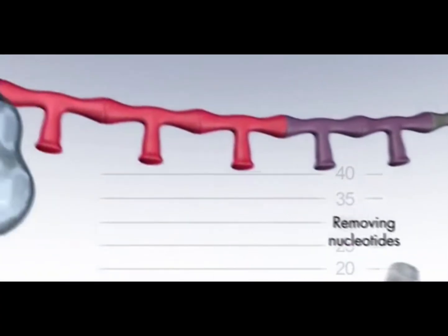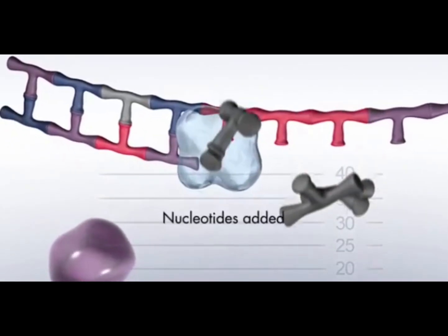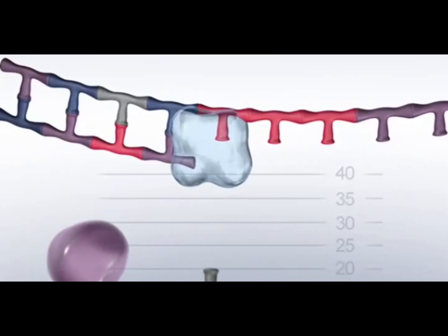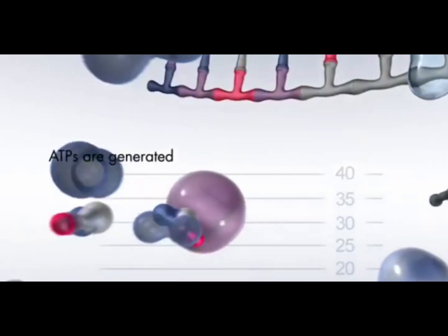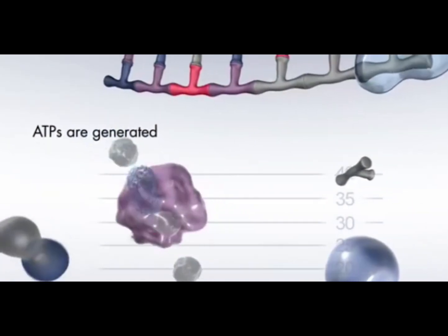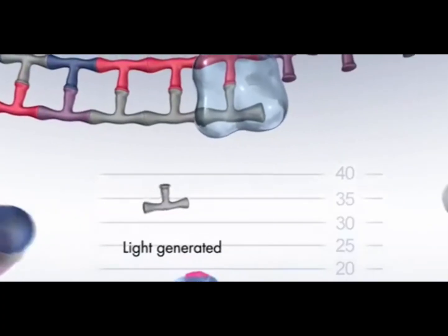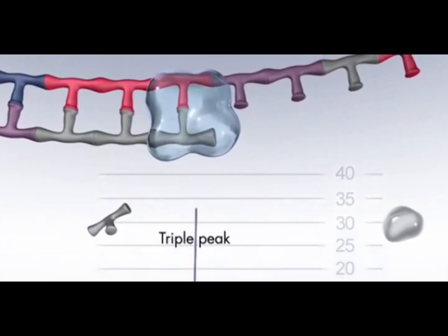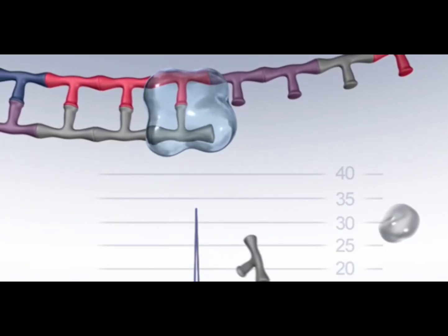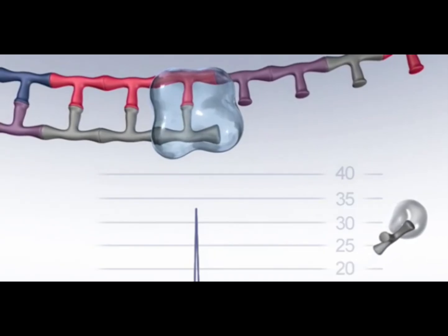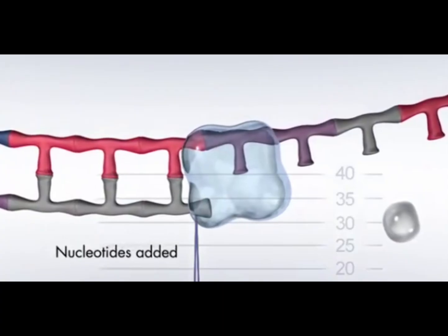So it initially uses the emulsion PCR technique to construct the colonies required for sequencing and removes the complementary strand. Next, a single-stranded sequencing primer is hybridized to the primer binding region, and the 4 different dNTPs are then sequentially made to flow in and out of the wells over the colonies. When the correct dNTP is enzymatically incorporated into the strand, it causes release of pyrophosphate. In the presence of ATP sulfurylase and adenosine phosphosulfate, the pyrophosphate is converted into ATP. This ATP molecule is used for the luciferase-catalyzed conversion of luciferin to oxyluciferin, which produces light, and that can be detected with a camera.